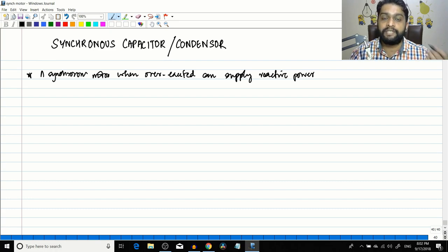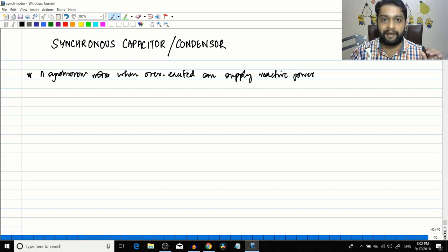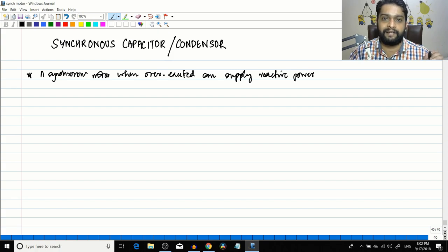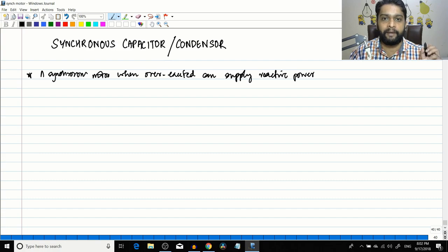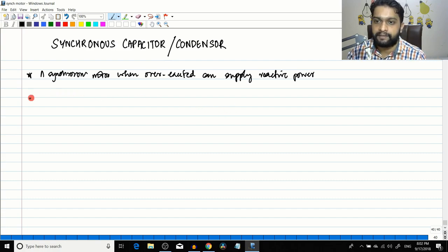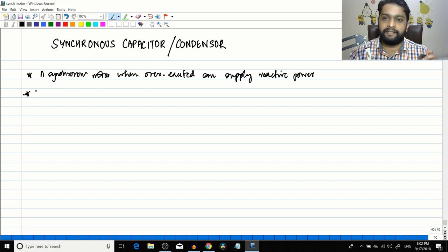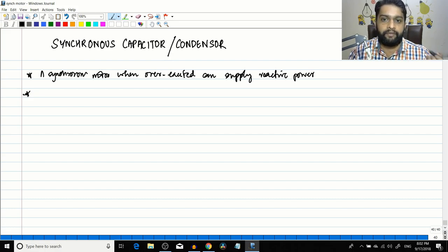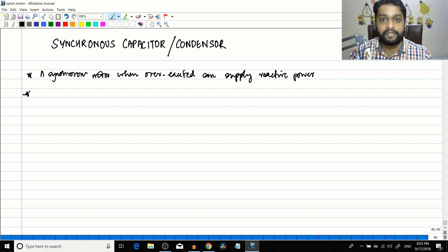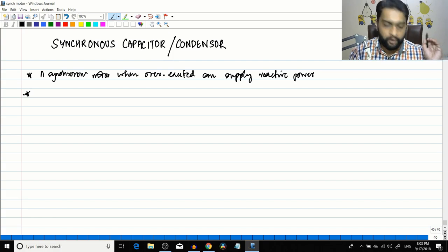They will be in their no-load condition and will just be used for power factor correction. So what we are discussing here is that the synchronous motor can supply reactive power when in an over-excited condition, and in some industries the synchronous motor is purchased only for this power factor correction. There the synchronous motor does not drive any load - it is in the no-load condition.